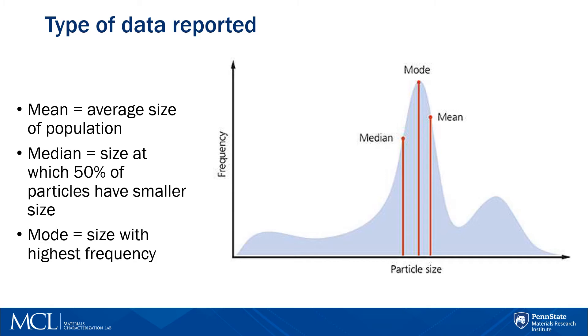Now let's go over what data are reported by laser diffraction and look into distribution statistics. The choice of statistical parameter will depend on how the data will be used and what they will be compared with. To report the most common particle size in a distribution, we can choose between the following parameters: mean — the average size of the population; median — the size at which 50% of particles have a smaller size; and mode — the size with the highest frequency.